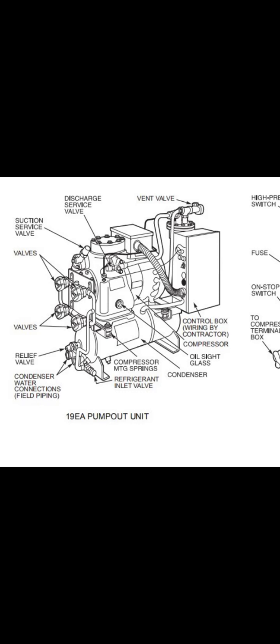What is the main point? Keep running water in the condenser and in the cooler. Otherwise, freeze up occurs in the tubes if you do not run it. Water is there in the pipeline. If the water does not run, the remaining water will freeze up and make cracks or leakage, which is the problem. So keep it running until the pump out procedure is finished.